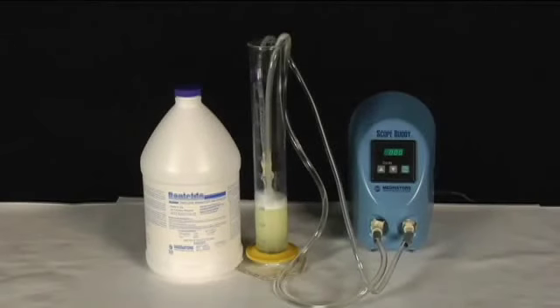If the unit is to be left unused, such as overnight or over the weekend or holiday period, it should be left full of decontamination fluid or clean rinse water. This maintains pump head decontamination, provides lubrication, and facilitates priming. During this period, do not purge or rinse any fluid from Scope Buddy. However, the tubing can be detached from the unit during this period, rinsed, and hung to air dry. Prior to use, after this decontamination procedure, the decontamination solution should be flushed from Scope Buddy using rinse water.